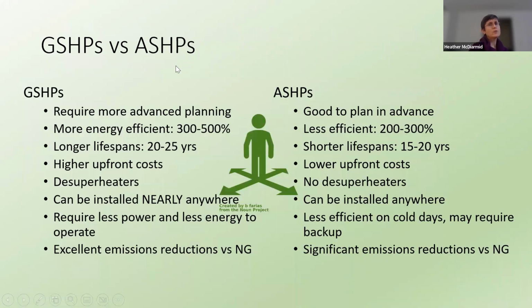Ground source heat pumps differ in a few aspects from air source heat pumps. You have a lot more infrastructure that you have to get set up for ground source heat pumps, so they require a lot more advanced planning. But you do get that greater efficiency. They are on average for heating 300 to 500% efficient over the heating season, whereas an air source heat pump is 200 to 300. Still impressive, but not quite as high. They have a longer lifespan, 20 to 25 years instead of 15 to 20. Of course, they have higher upfront costs, but you can get desuperheaters with the ground source heat pumps.